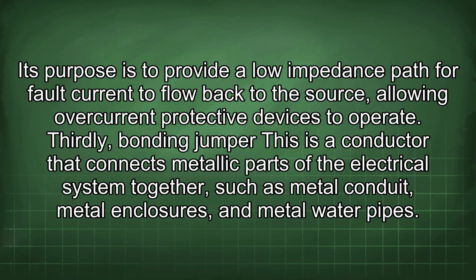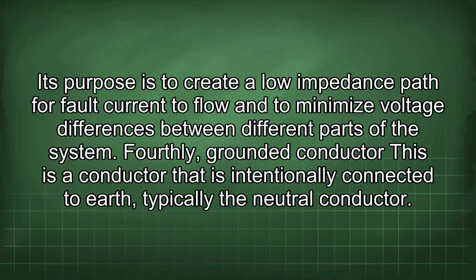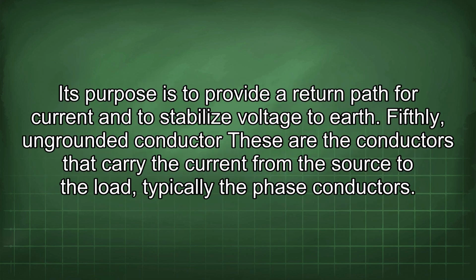Thirdly, bonding jumper. This is a conductor that connects metallic parts of the electrical system together, such as metal conduit, metal enclosures, and metal water pipes. Its purpose is to create a low impedance path for fault current to flow and to minimize voltage differences between different parts of the system. Fourthly, grounded conductor. This is a conductor that is intentionally connected to earth, typically the neutral conductor. Its purpose is to provide a return path for current and to stabilize voltage to earth.